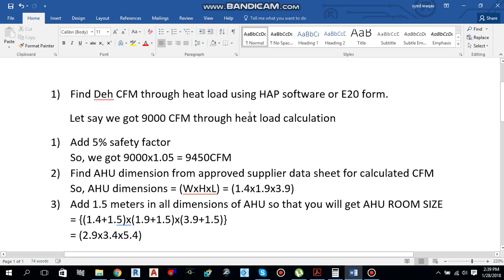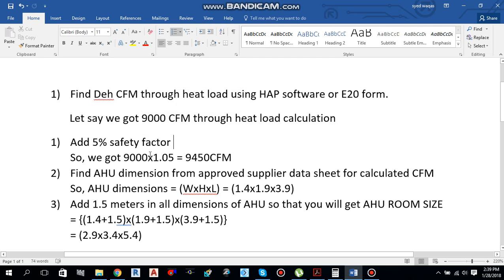After using the HAP software, let's say we got 9000 CFM through heat load calculation. We have to add a 5% safety factor to keep on the safe side. To add this 5% safety factor, multiply 9000 by 1.05 — you will get 9450 CFM.